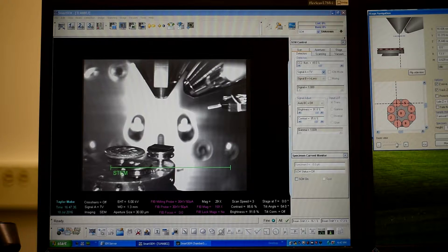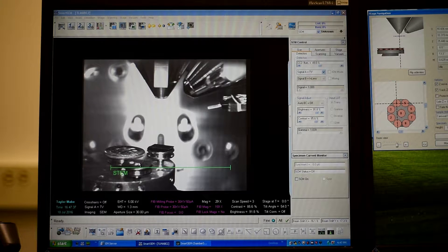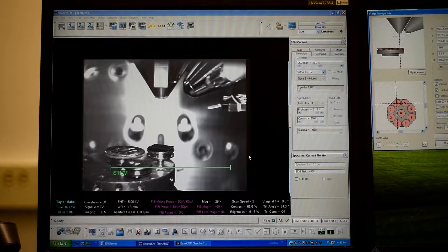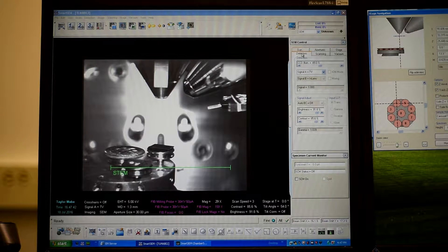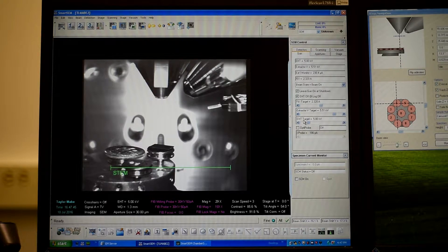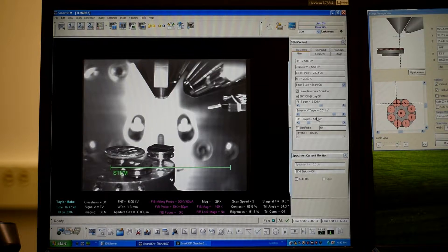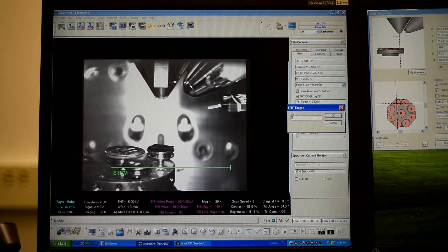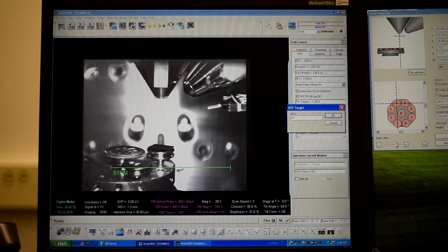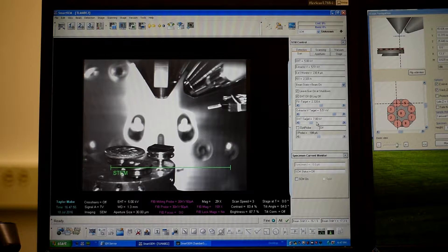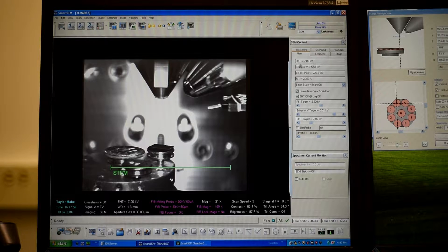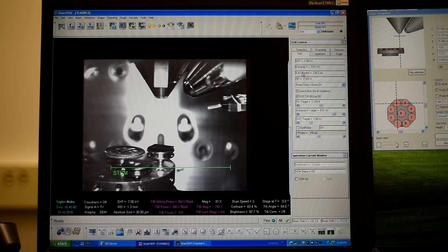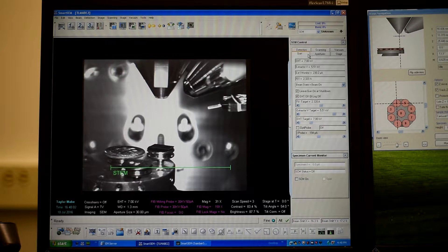If we go back to the other screen, you can see that it moved it to here. So now what we can do is the gun's warmed up. So if you go to the gun tab, you can set your EHT target right here. So if we wanted to do, say, 7 kV as opposed to 5, we just hit 7 and then hit enter. So that changed the target. And that will correspondingly change the actual value. So you can change any of these values here.